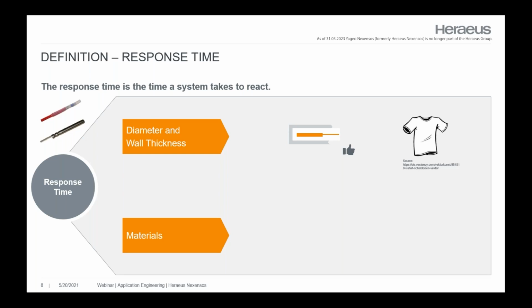The next factor that influences the response time is the material. Again, a little drawing here of a housing sensor element. We have to say that even for thin film technologies, there would be a bad response time if the tube were only filled with air and not with a special filling material.